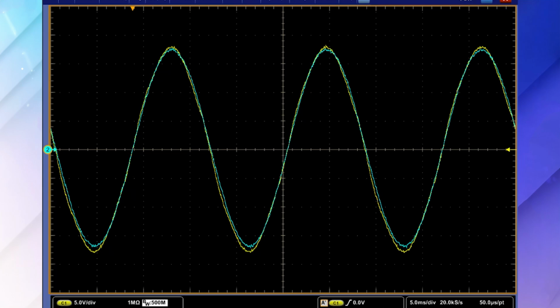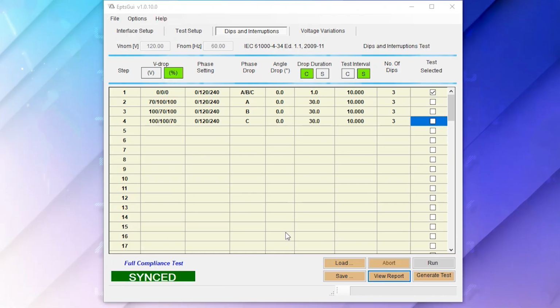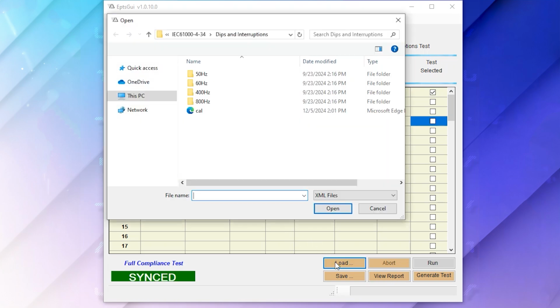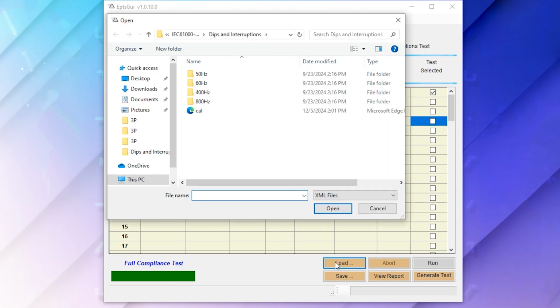Let's go ahead now, take a look at the software again, and run the test for IEC 61000-4-34. Now that we've finished the test setup menu, we're looking to run the test. We're on the dips and interrupts menu now. Let's go ahead and click load in the lower right corner. From this menu, we can select the frequency range. We're interested in 60 Hz today.